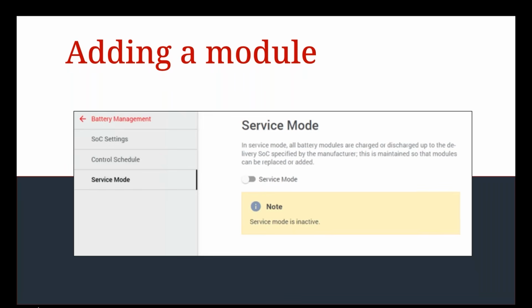Yes, of course. There's no super hard or harsh limitation prohibiting battery modules from being added, but just something to keep in mind: within the first 2 years, the modules would operate at the same SOH. So if you add another module before 2 years, you won't get any performance limitations. If you add a battery module after 2 years, you can still do it, but keep in mind the new module will operate at the lowest SOH of the remaining stack. So it wouldn't perform at 100% capacity due to the setup, but it's still possible.